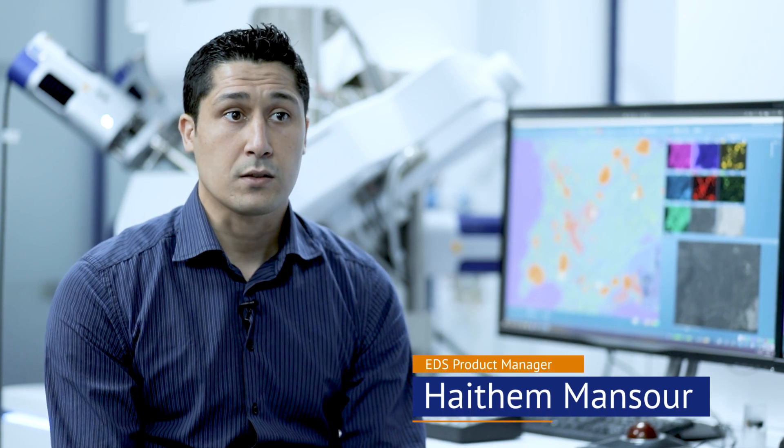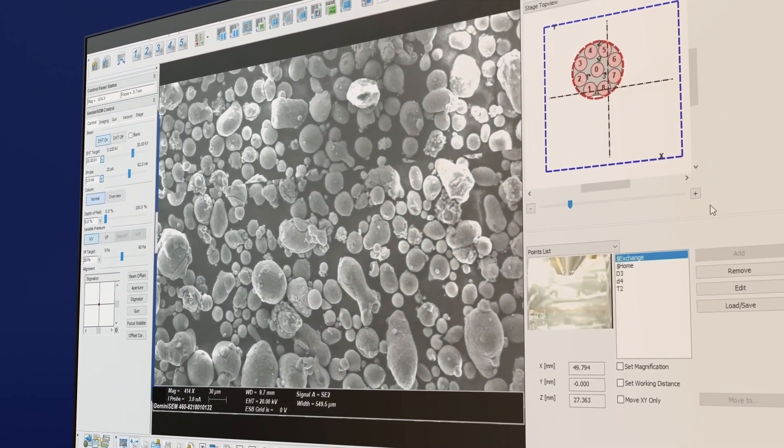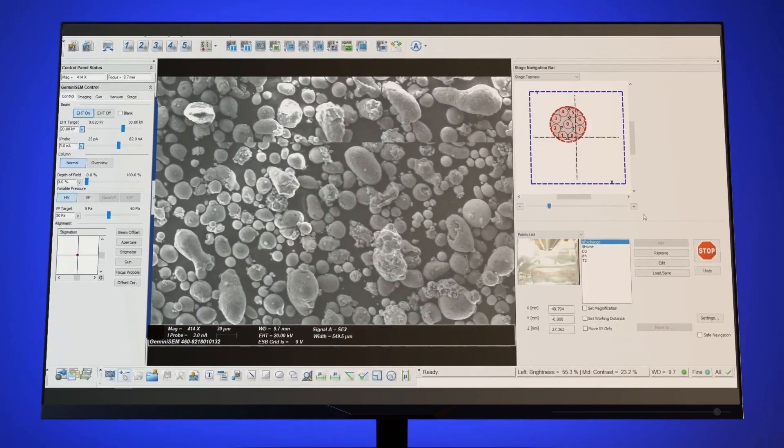Imaging in the SEM has always been in black and white. We mainly use two signals: secondary electrons and backscattered electrons that result in a black and white image. Secondary electrons typically give information about topography; backscattered electrons give us indicative information about composition. Users usually trust these two imaging techniques and use their instinct to find their areas of interest.